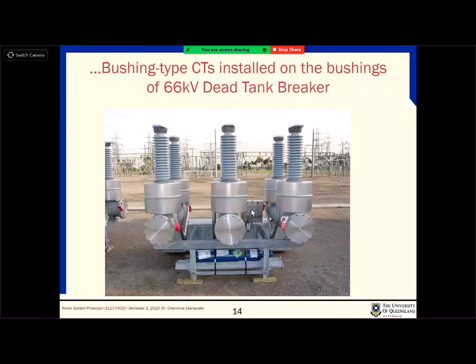Usually, nowadays you can't use these sort of breakers in suburban areas. They are very, very loud when they operate, right? That's why we go for SF6 and oil breakers and all these things. These old types, just for your information, you probably may not be able to see in future, right? But from the CT point of view, the important part is that you measure the current on the CTs and then take the appropriate action.